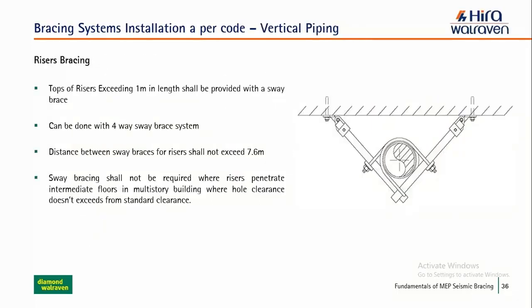Risers have their own standards to consider for the bracing system. If the top of the riser exceeds 1 meter in length, it shall be provided with sway brace, and a four-way brace can be used, because it's more logical to use a four-way brace in risers because they are vertical. The distance between sway braces for a riser shall not exceed 7.6 meter. So this is the riser as we have here.